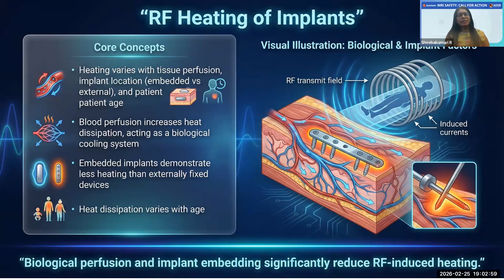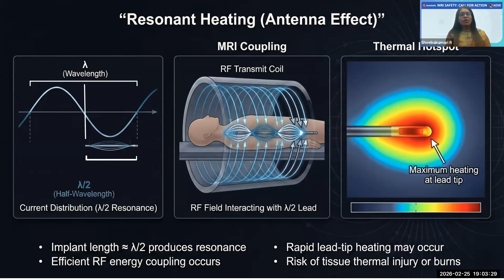Coming to the most important concern with the RF pulse, which is resonant heating. When the implant length matches half the wavelength of the radio frequency pulse, perfect coupling forms between the radio frequency pulse and the implant, resulting in a sudden rise in temperature at the lead tips. This is called resonant heating. The resonant wavelength of the radio frequency pulse is modified by the dielectric property of the tissues, and it also depends upon the field strength.